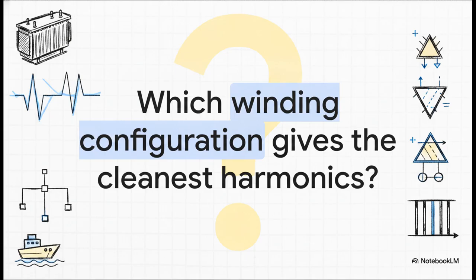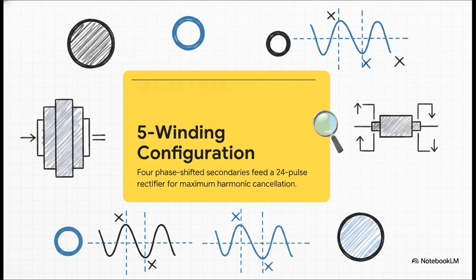Okay, before we wrap this up, let's do a quick check and test your mental map of what we've covered today. Think back to those multi-pulse rectifier designs we mapped out earlier. If you are the engineer responsible for ensuring the absolute cleanest harmonic performance, the minimum interference on your vessel's grid, which transformer configuration are you writing into the spec? Got your answer? To get the cleanest possible harmonic performance on your single-line diagram, you've got to specify the 5-winding configuration feeding a 24-pulse rectifier system. Why? Because more phase-shifted secondaries means more harmonic orders get canceled out before they ever reach the switchboard. It is absolutely the ultimate solution for inherent, built-in harmonic mitigation.